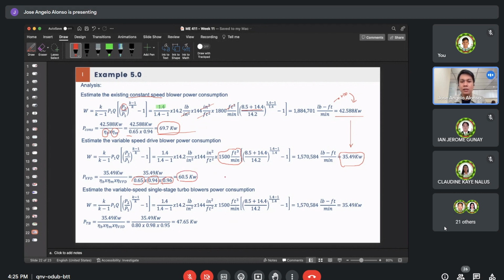So there's a reduction of 9.2 kilowatts when we use a VFD compared to the existing constant speed setup. That's not bad, right? There's already savings involved. But that won't be our final basis — we'll convert that later to dollars to determine if it's cost effective or not.